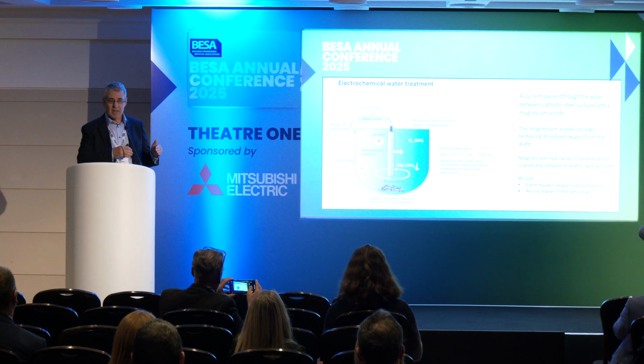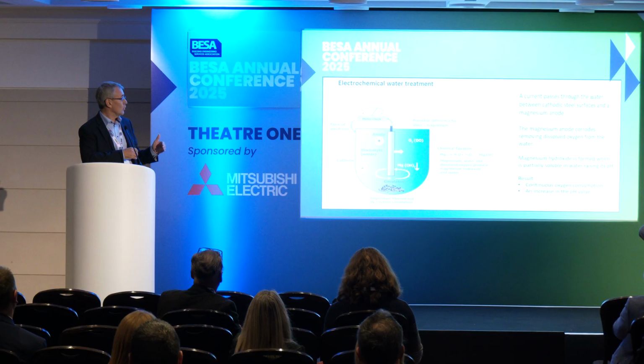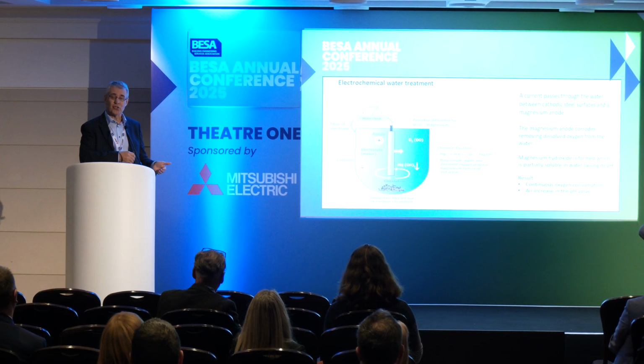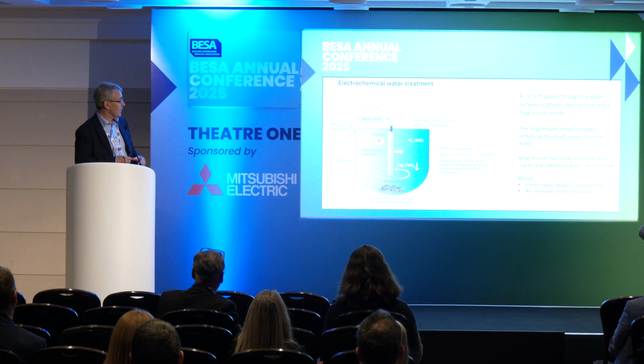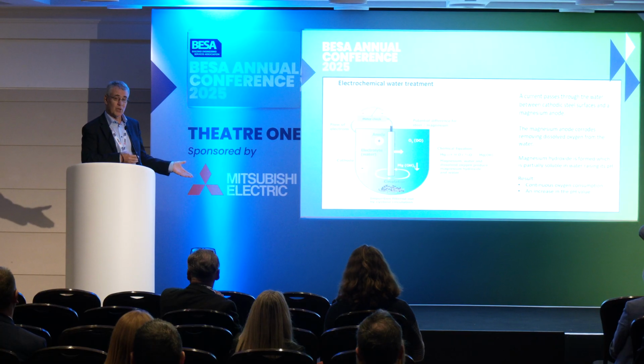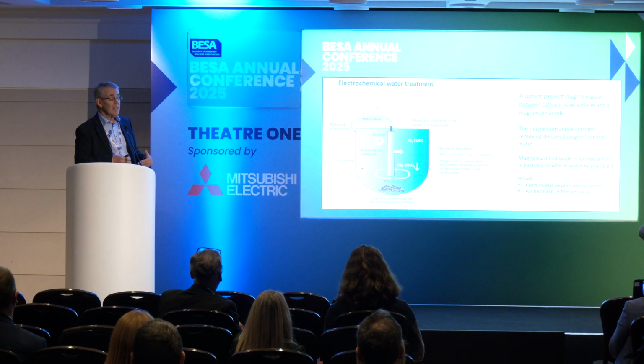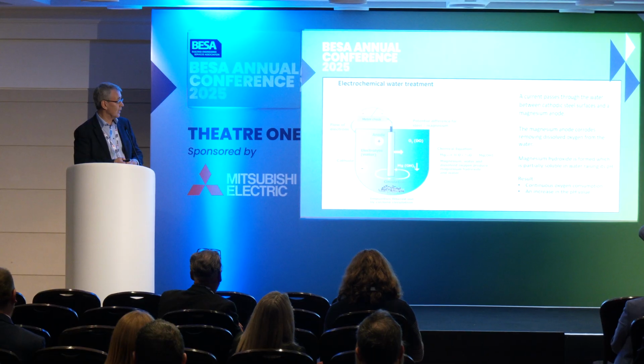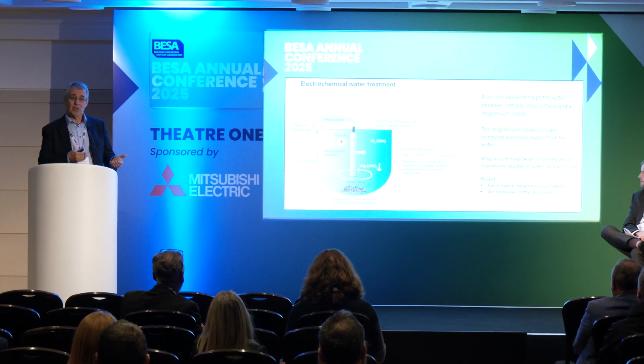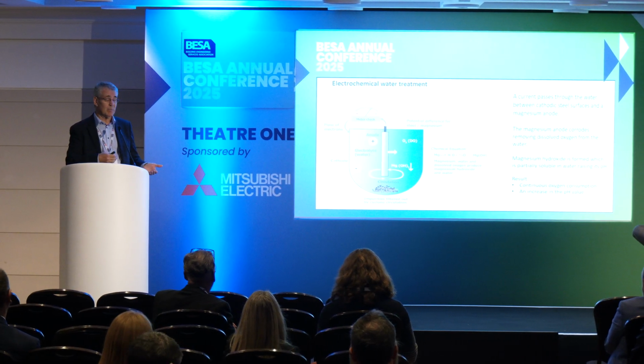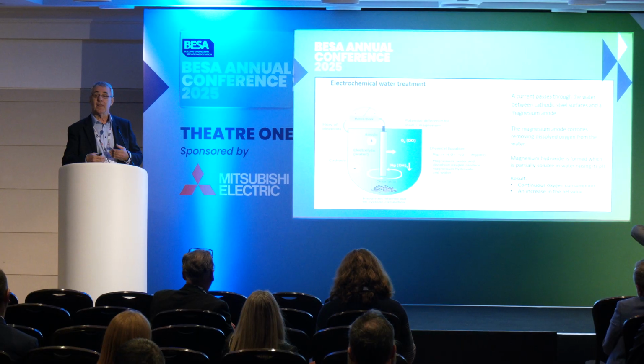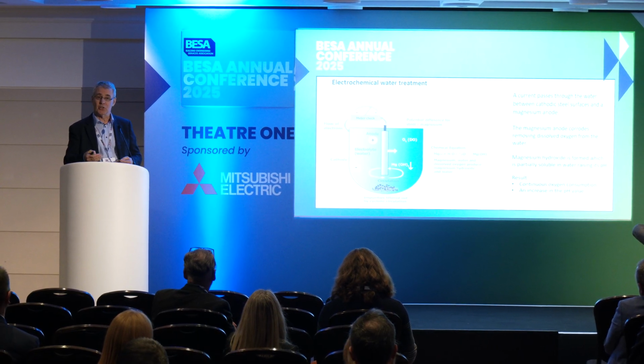So a chemical-free solution, also known as an electrochemical water treatment solution, aims to achieve that: to drop the oxygen level but to control pH. It does it by means of a reaction vessel. You pass a current through the water between your cathodic steel surfaces and a magnesium anode. The magnesium anode then dissolves, it corrodes, and as it corrodes, it absorbs oxygen that's passing through it, which helps you to drop the oxygen level in the system. The magnesium hydroxide, which is the corrosion product of magnesium, some of that then dissolves into the water, and that's what raises the pH and gets you into the good pH range.